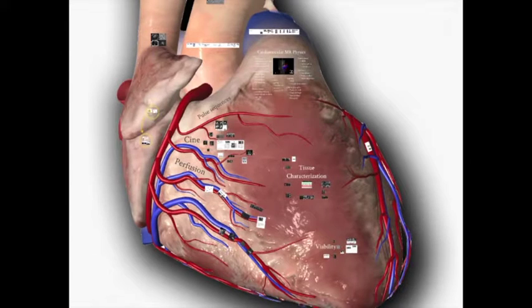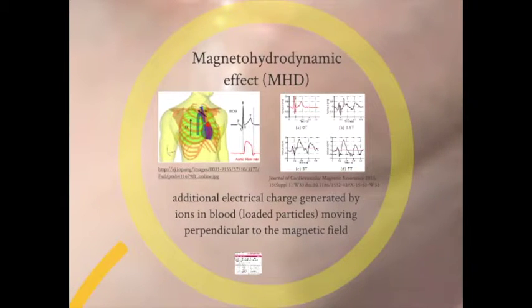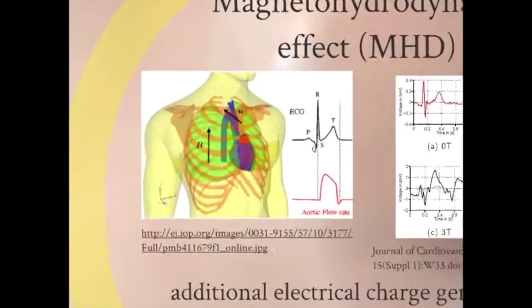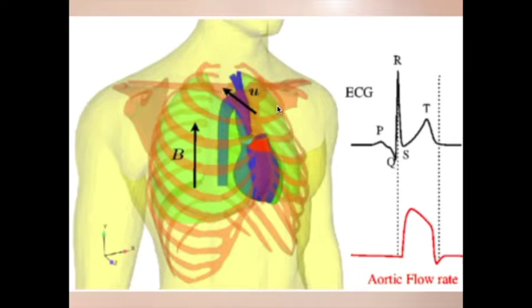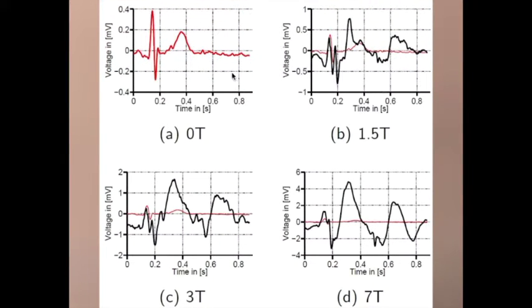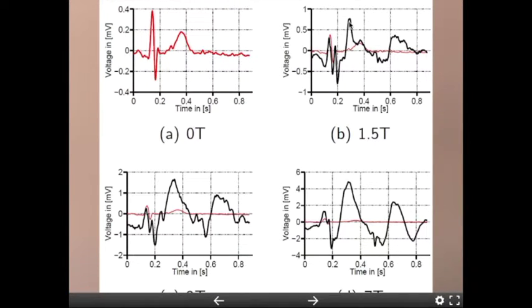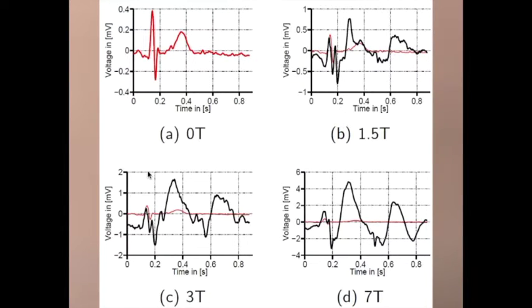The most important issue at 3 Tesla is gating. One of the problems when we put a patient in the magnet is the magnetohydrodynamic effect — not something from the Avengers. As blood comes across the aortic arch, it generates a signal at the part of the cardiac cycle where there's the most aortic flow. The scanner sees this artifact right at the location of the T-wave. As field strength goes up, this artifact gets worse and worse — so more artifacts with higher field strength.